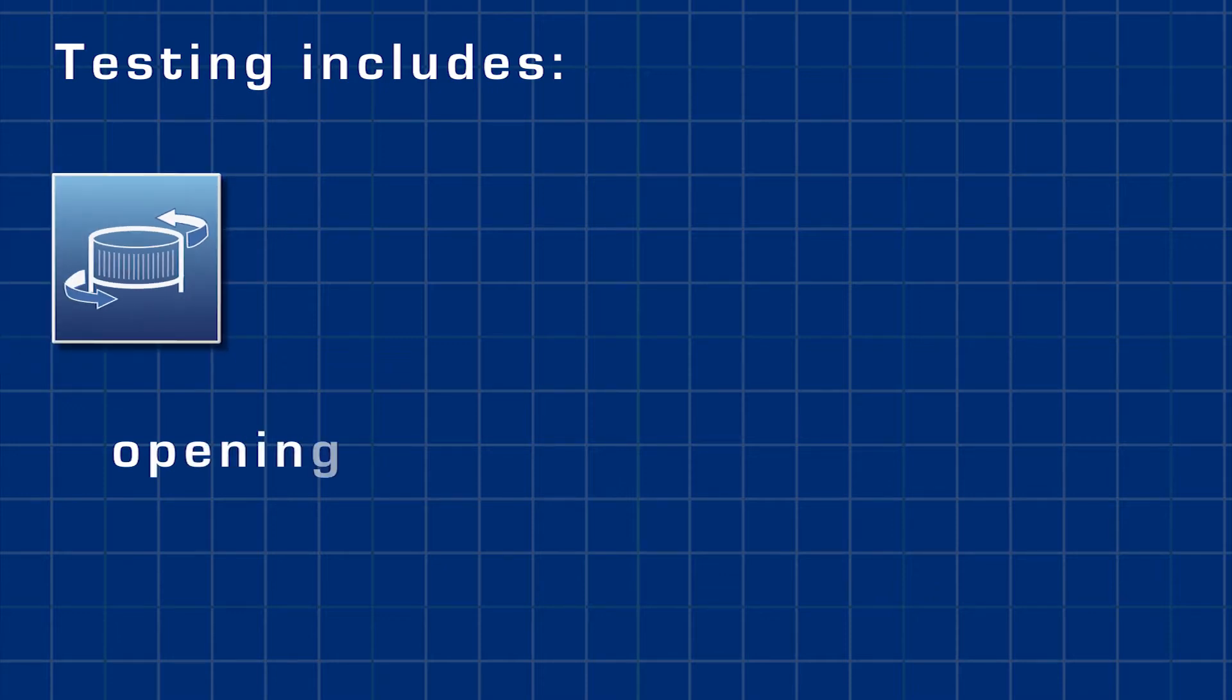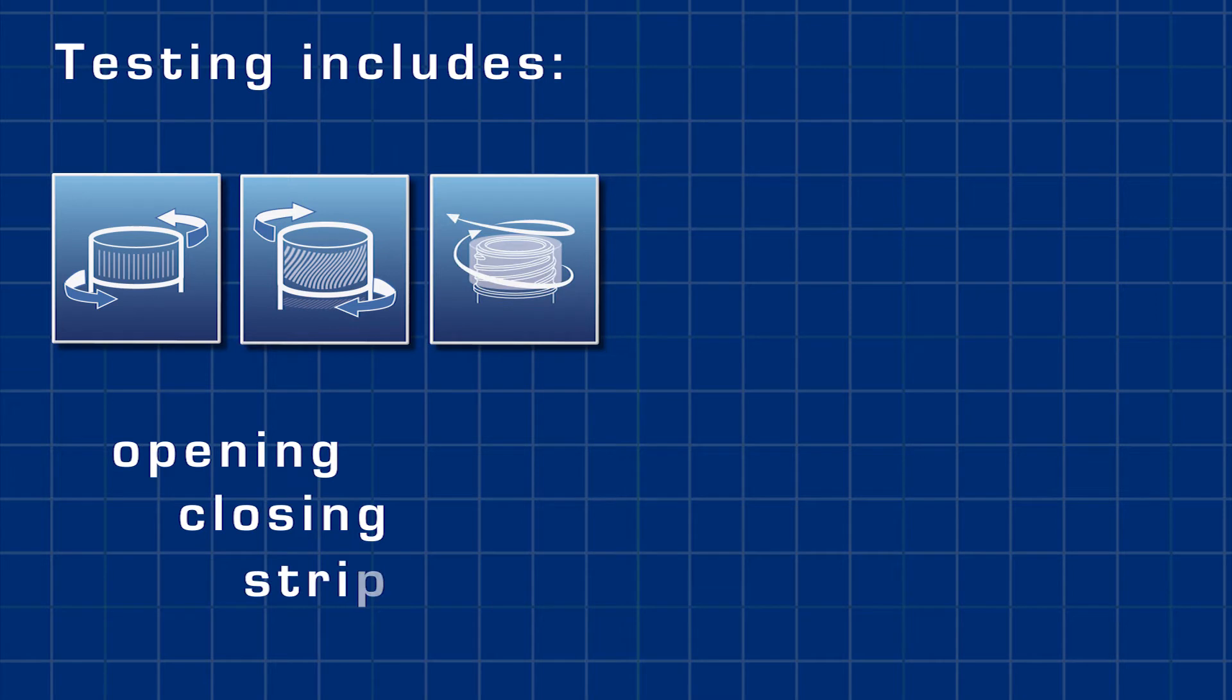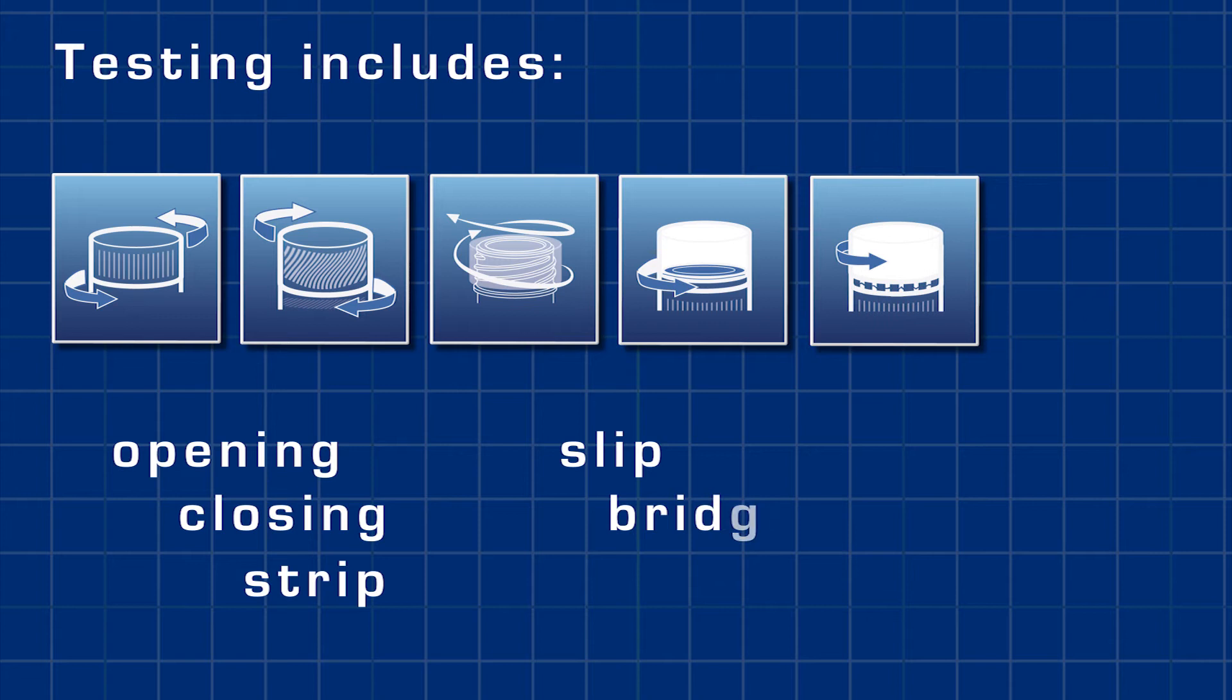Testing includes the measurement of opening, closing, strip, slip, bridge, and reverse ratchet torque.